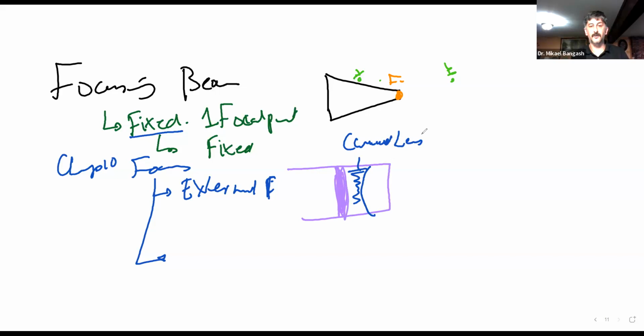And what that curved lens was going to do is cause whatever sound waves were produced by the PZT, once they hit that curved lens, to start refracting. That causes the beam, instead of traveling in straight lines, to start to converge. And this will cause the beam to focus at a point. But that was what we call external focus, which is fixed. Did that make sense?